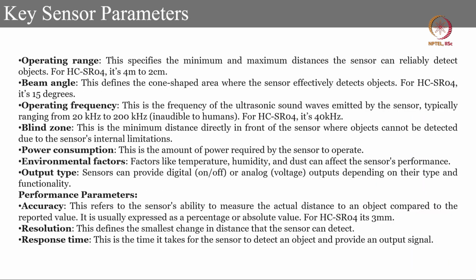There are sensor parameters that we need to consider, particularly when you talk about an ultrasonic sensor. There is operating range, beam angle. The beam angle generally is about 15 degrees. Operating frequency can be from 20 kilohertz to 200 kilohertz. Blind zone is the minimum distance where the sensor will not work. Power consumption is the amount of power required for the sensor to operate. Environmental factors like temperature, humidity and dust can affect the sensor performance. The output of the sensor can be digital or analog depending on type and functionality.